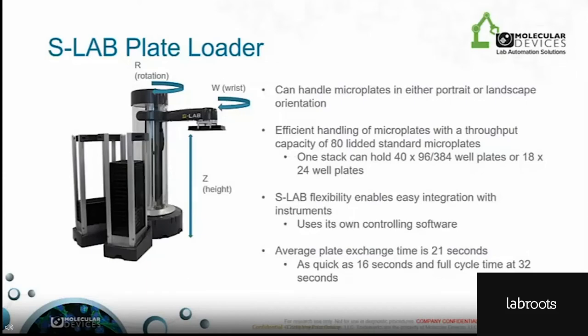The robotic arm or plate loader takes over for the scientist and helps bring together an automation work cell by employing processes to move your labware to each instrument within the work cell. The S-Lab plate handler is designed as an entry-level automation solution for multiple applications and ease of use. It allows the gripper arm to hold labware in either portrait or landscape orientation and employs its own controlling software that enables the robotic arm to work together with the other instruments.